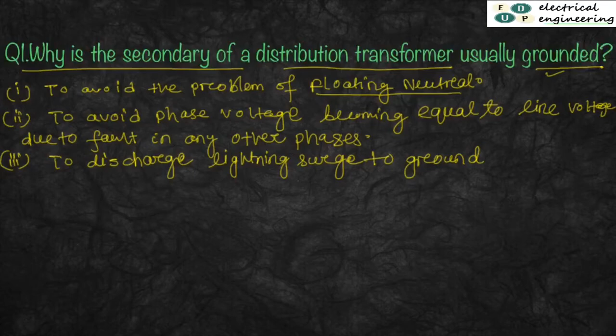Okay, now let's first discuss what is floating neutral and how this can be avoided by grounding the secondary of the distribution transformer. So floating neutral. Suppose there is a distribution transformer, let's say 11 kV by 415 volt, with delta Y connection. Let me just draw. This is your primary winding, delta connected, and this is your secondary winding, star connected.